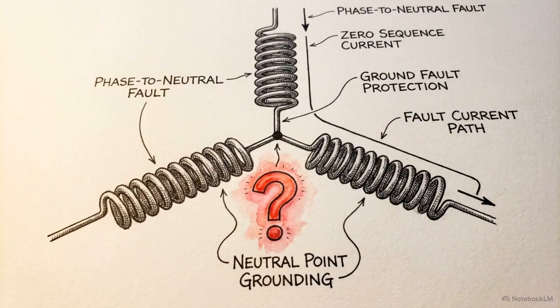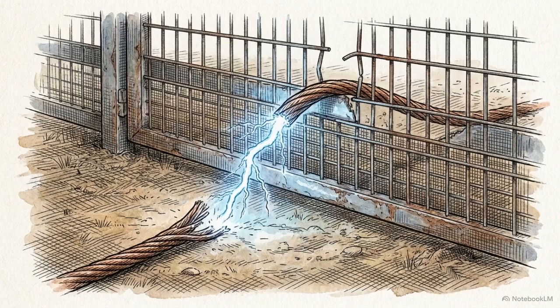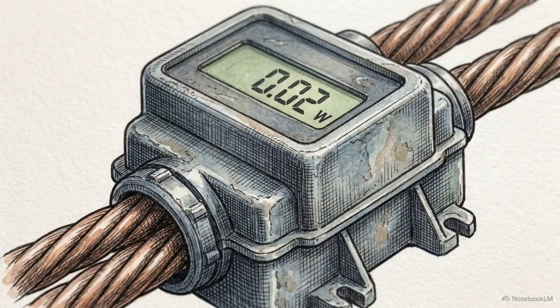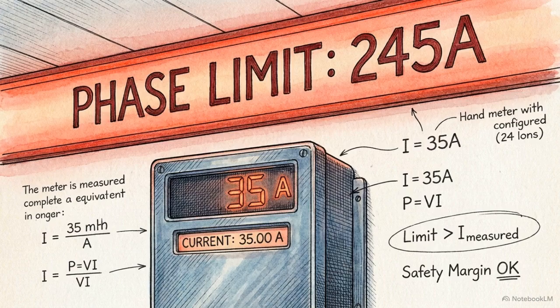However, overcurrent relays have a critical blind spot: earth faults occurring near the neutral point of a grounded Y winding. If a phase conductor makes contact with grounded equipment, it routes massive current directly into the earth. But because of where the fault sits on the winding, the current registering on the phase lines remains very low, keeping it completely hidden below our 245 amp phase pickup setting.